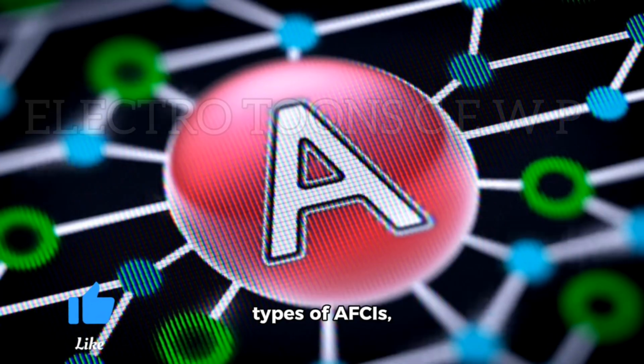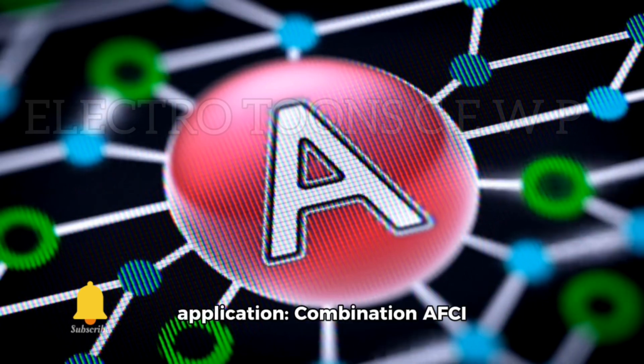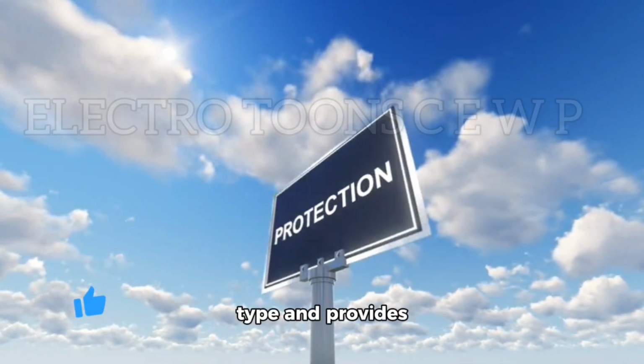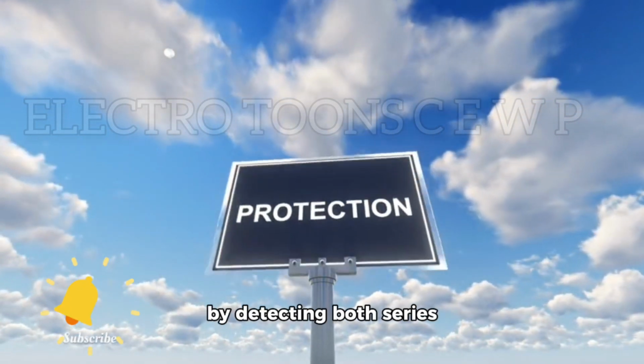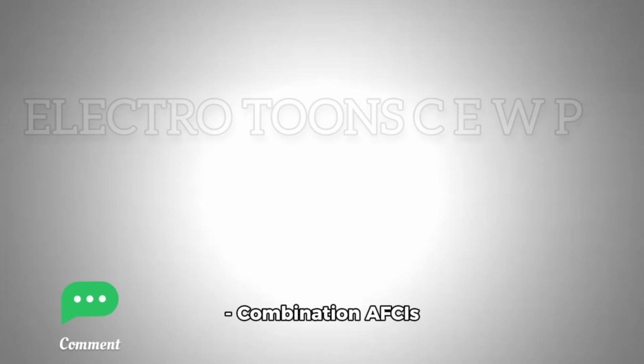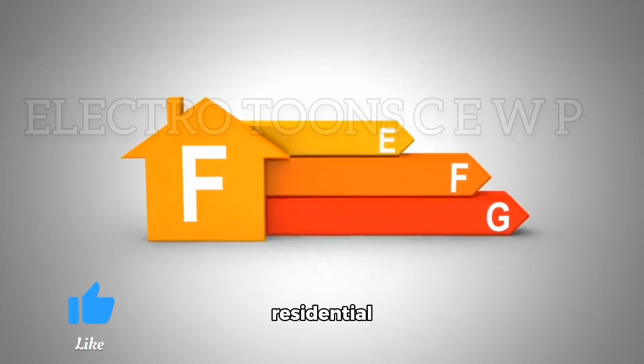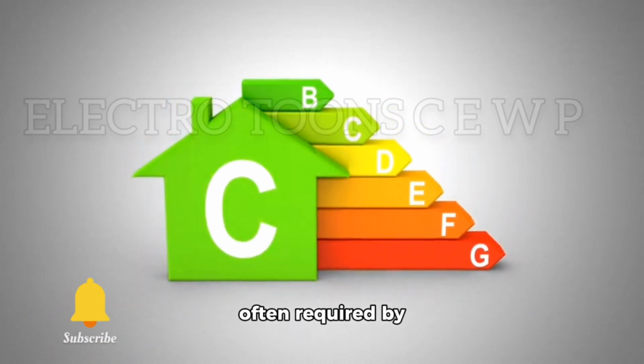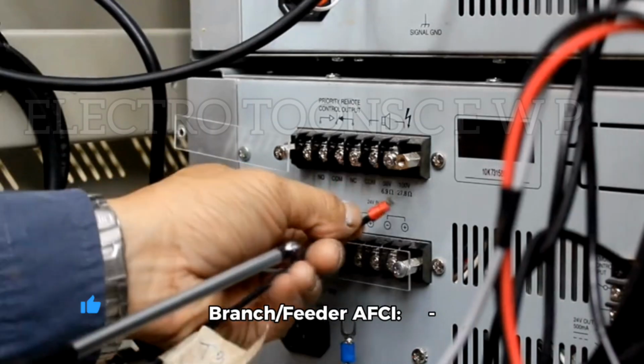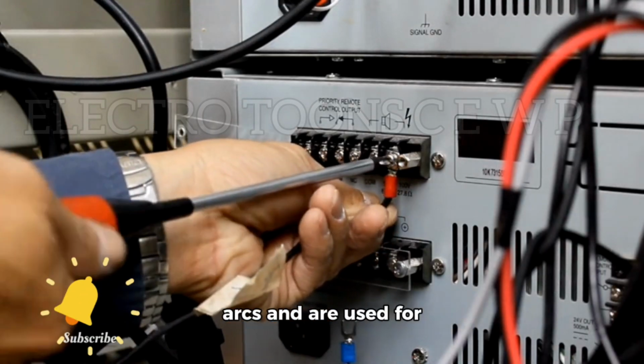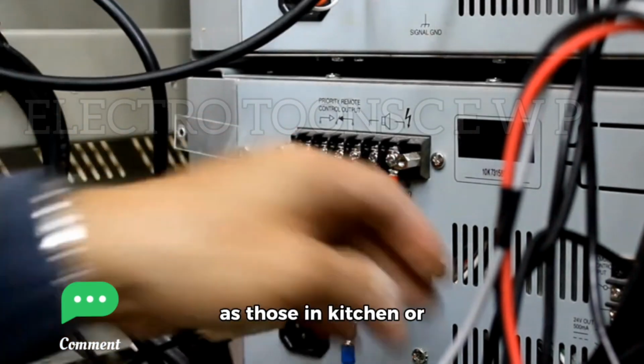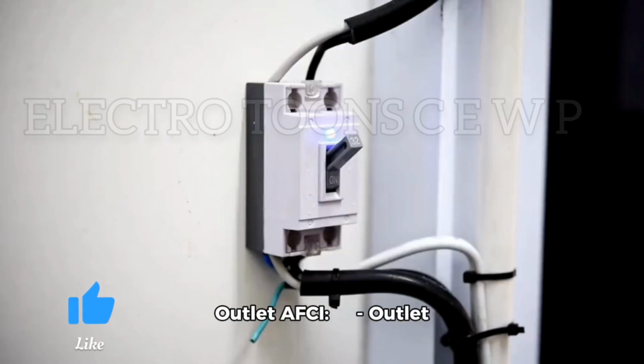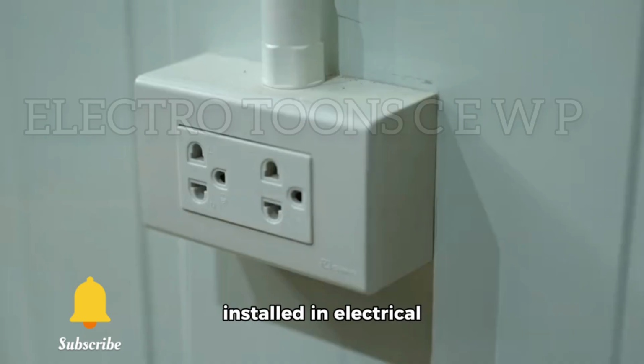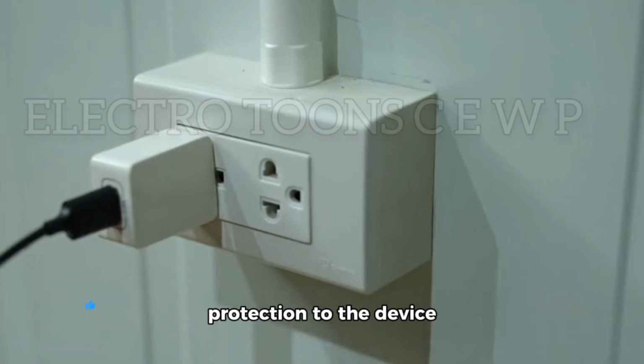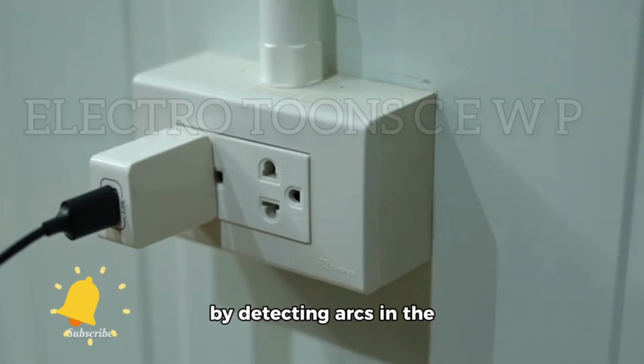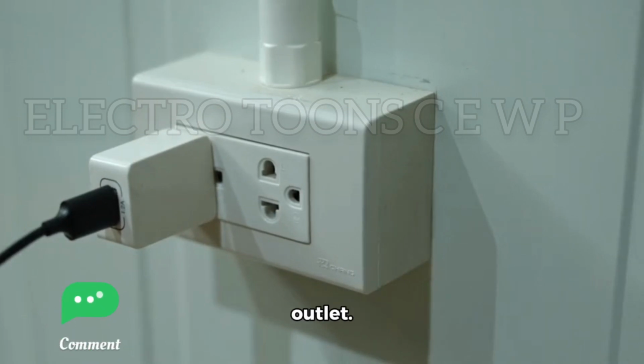There are different types of AFCIs depending on their application. Combination AFCI. This is the most common type and provides comprehensive protection by detecting both series arcs and parallel arcs. Combination AFCIs are typically used in residential applications and are often required by modern electrical codes. Branch feeder AFCI. These detect only parallel arcs and are used for specific circuits such as those in kitchen or living areas. Outlet AFCI. Outlet AFCIs are designed to be installed in electrical outlets and provide protection to the device plugged into the outlet by detecting arcs in the wiring connected to that outlet.